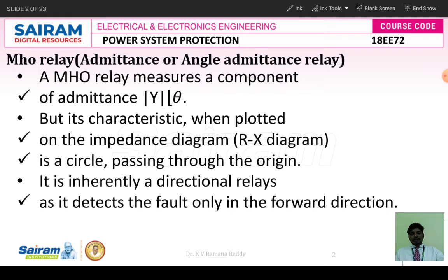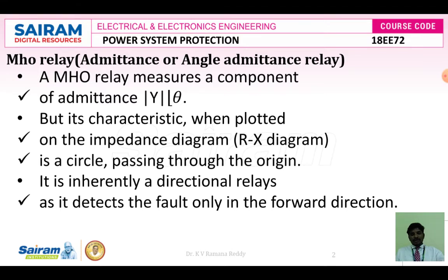Mod of Y is the magnitude of admittance at an angle of theta, which is expressed in polar form. But its characteristic, when plotted on the impedance diagram, simply called the RX diagram, looks like a circle passing through the origin, and it is inherently a directional relay. It detects the fault only in the forward direction, not in the reverse direction.